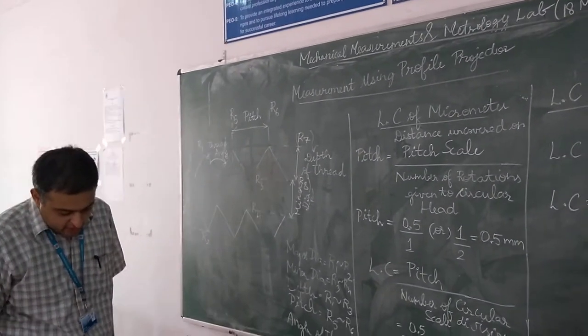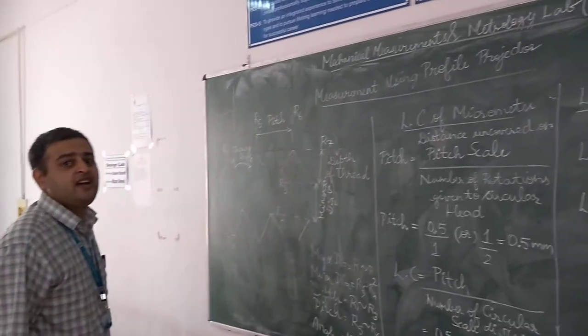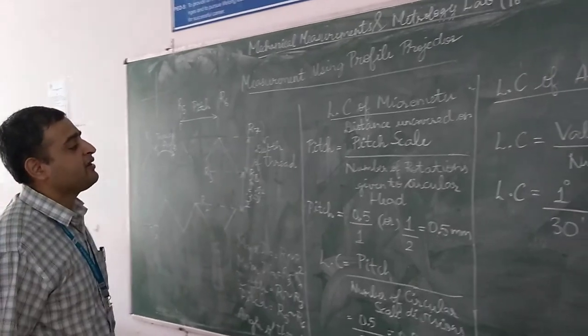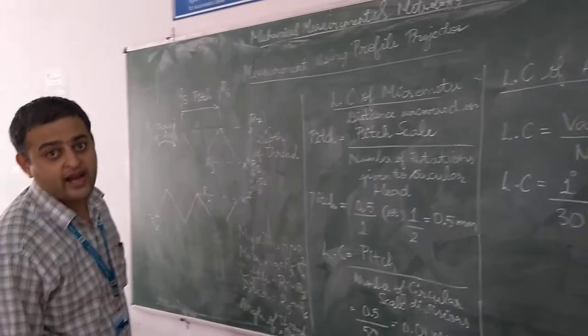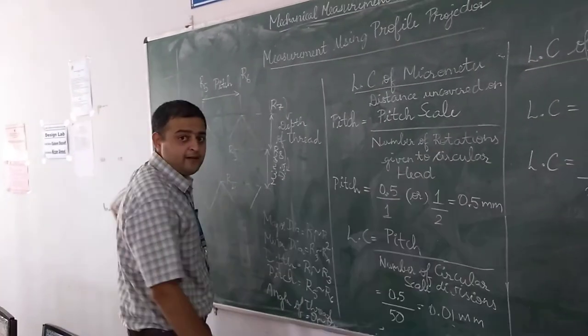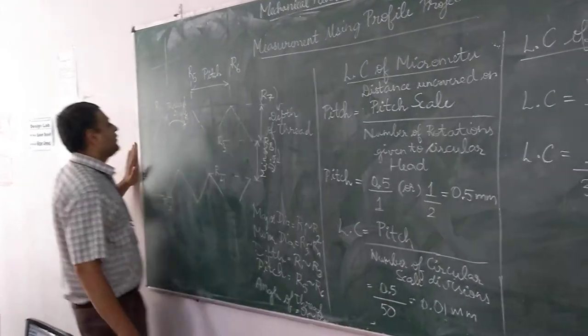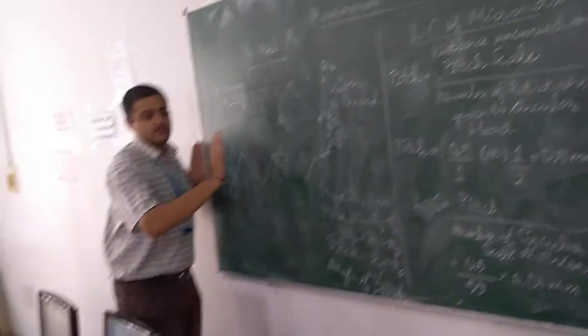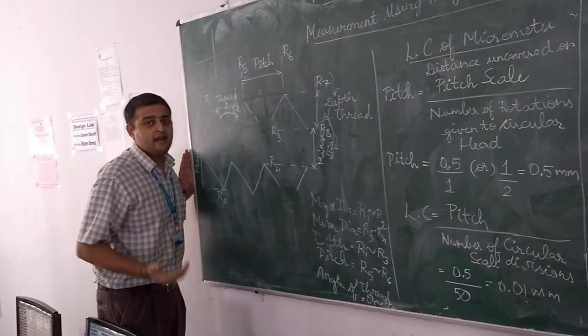This experiment involves measurement of screw thread parameters using a profile projector. We are using the optical principle of magnification to examine the threaded specimen and find various thread parameters. The main thread parameters we are going to find are the pitch, major diameter, minor diameter, depth of the thread, and thread angle. The optical projector magnifies the image of the thread specimen so that measurements can be made easily.